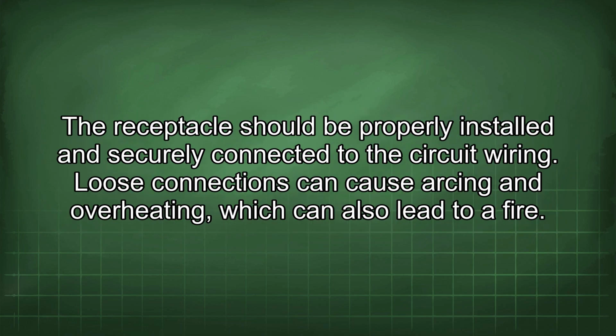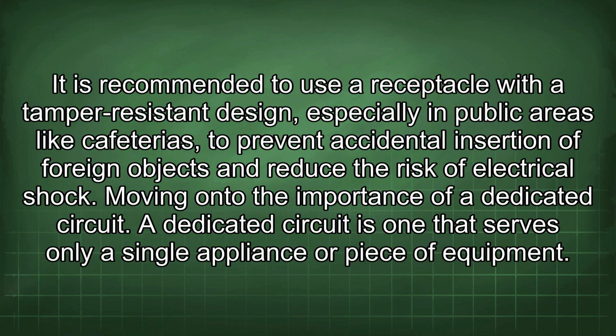The receptacle should be properly installed and securely connected to the circuit wiring. Loose connections can cause arcing and overheating, which can also lead to a fire. It is recommended to use a receptacle with a tamper-resistant design, especially in public areas like cafeterias, to prevent accidental insertion of foreign objects and reduce the risk of electrical shock.